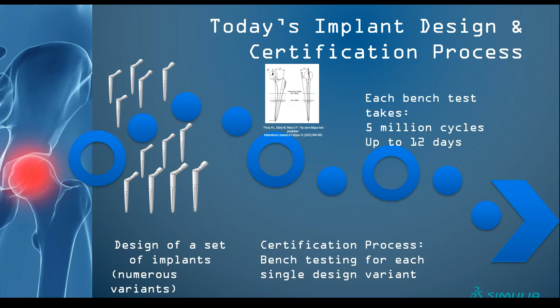Now imagine that you have a new implant with 200 different geometric variants. Following the certification rule, every single variant needs to be tested on the workbench. Assuming that you have 40 test benches available to you, and with a test time of 12 days per implant, you get a total workbench testing time of about 60 days. Thus, certification of a new implant series requires more than 60 days once the final designs are available, given that you're not going to change any of those designs and have to retest them again.